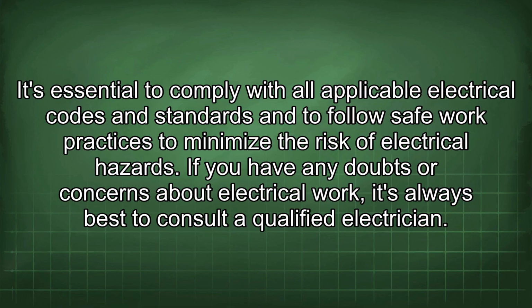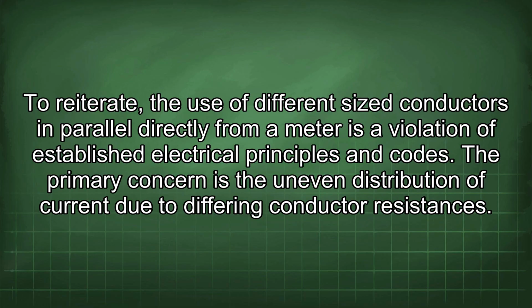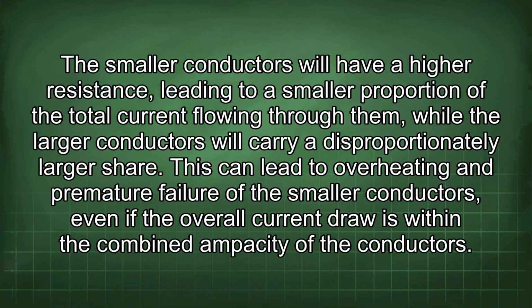To reiterate, the use of different sized conductors in parallel directly from a meter is a violation of established electrical principles and codes. The primary concern is the uneven distribution of current due to differing conductor resistances. The smaller conductors will have a higher resistance, leading to a smaller proportion of the total current flowing through them, while the larger conductors will carry a disproportionately larger share. This can lead to overheating and premature failure of the smaller conductors, even if the overall current draw is within the combined ampacity of the conductors.